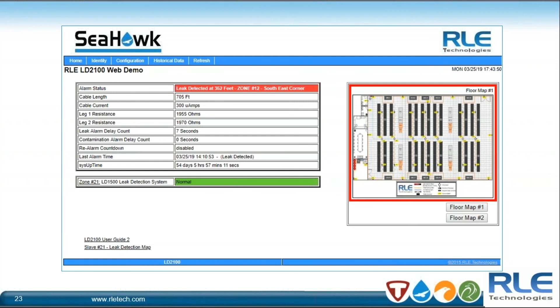So here's a kind of neat data center design for a large area. We took one of our larger 5200 systems, which can handle up to 10,000 feet of sensing cable, and deployed maybe 1,000 feet, where we got almost 2,000 feet of sensing cable. The biggest thing that allows us to do that, if you look right here in the middle, is a little component called an X connector, whose architectural design allows it to act as a splitter.